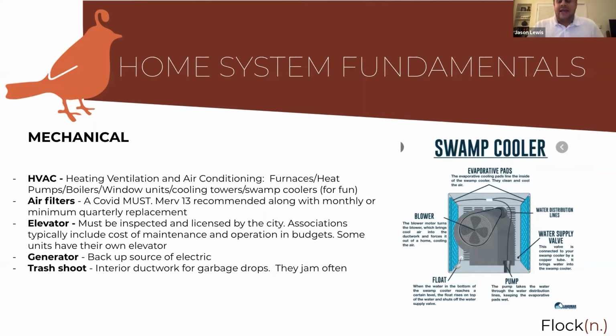For your own personal house, you probably want to rev that up every now and then just to make sure it's working. But for your condo building or mixed use development, you'll want to put that on either a semi-annual or quarterly PM - shorthand for preventative maintenance. Identify a contractor, have them conduct a regular inspection of the system, and make sure you're aware of anything going on. Some contractors will also recommend things you may not have heard of, such as a diesel fuel analysis, a load bank test, or a coolant check.